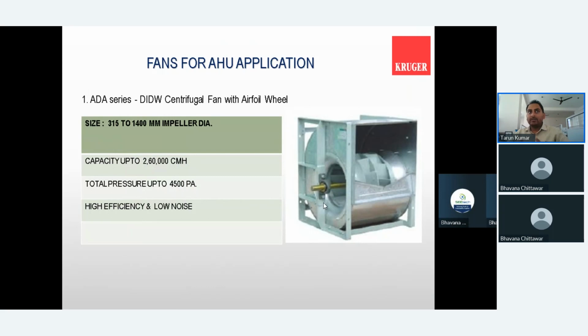Backward curve is used where static pressure is more than 50 mm, because due to high strength it can handle more static pressure. So always when our static pressure is more than 50 mm, we should preferably go with either the backward curve fan or the aerofoil curve fan. That again depends upon your efficiency requirement. Whereas the forward curve can generate less static pressure, up to 50 mm static, and for lesser efficiency we use the forward curve fan.